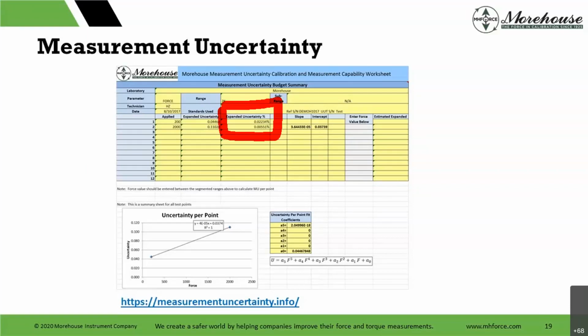This is one that came from a class where we did 2 points. What's important here is if you look at the expanded uncertainty that's calculated with all those things, the 5 R's, the E, the temperature specification, everything else, look at these measurements. At capacity, at 2,000 pounds, this is our Morehouse PCM machine. At 2,000 pounds, we're at 0.0055. However, at 200 pounds, we're at 0.022. Quite a bit of difference, right? You see people just blindly throw out on scopes, hey, I'm accurate to 0.006% of full scale. That doesn't tell the end user the whole picture, because it doesn't tell you how good they are at any point other than full scale.